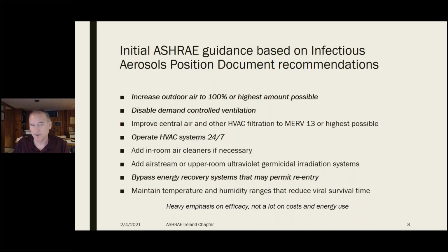Increase outdoor air to 100% or as much as possible. Disable demand-controlled ventilation. Upgrade filters to MERV 13 or as high as possible given efficiency. Operate HVAC systems 24/7. Add in-room air cleaners if you can. Add upper room ultraviolet germicidal radiation if you can. Bypass energy recovery because it may result in reentry. And consider modifying temperature and humidity to reduce viral survival time.